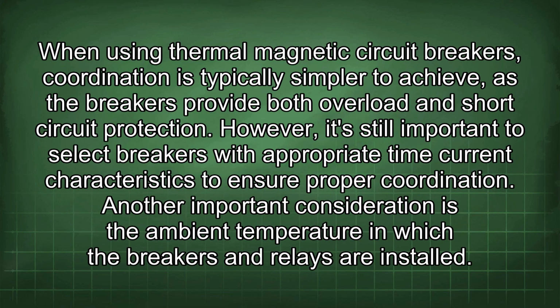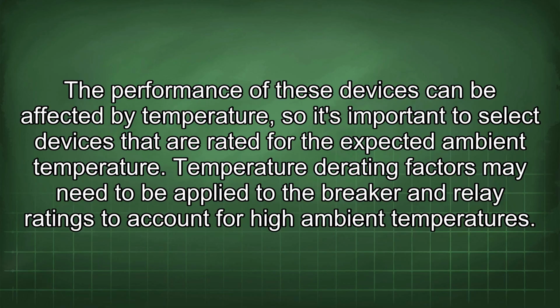When using thermal magnetic circuit breakers, coordination is typically simpler to achieve, as the breakers provide both overload and short circuit protection. However, it's still important to select breakers with appropriate time current characteristics to ensure proper coordination. Another important consideration is the ambient temperature in which the breakers and relays are installed. The performance of these devices can be affected by temperature, so it's important to select devices that are rated for the expected ambient temperature.